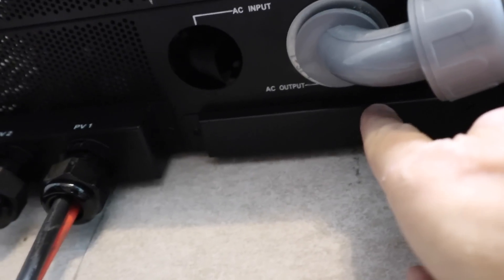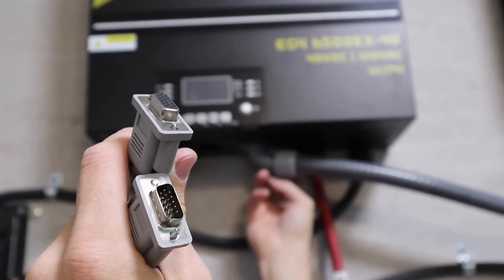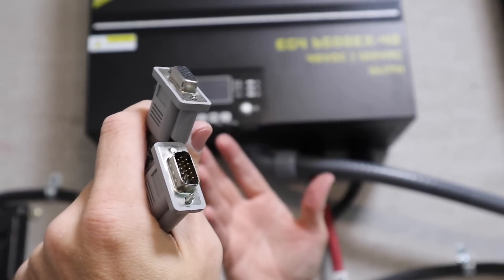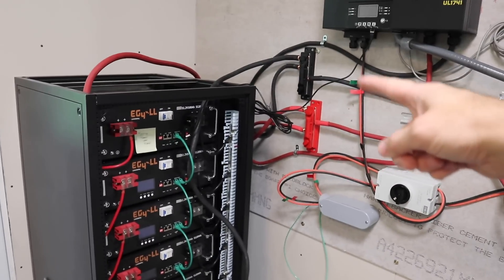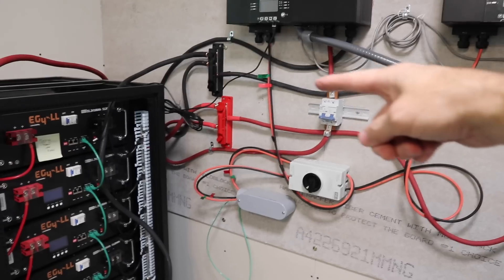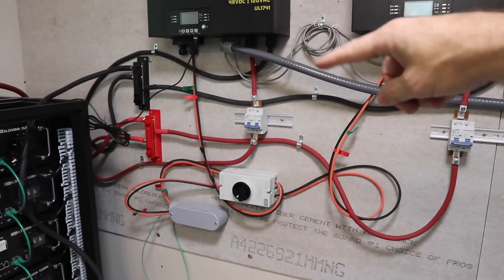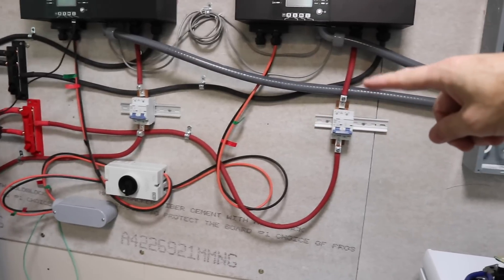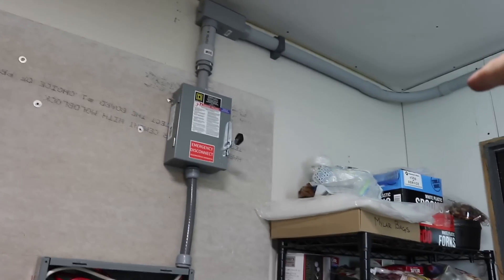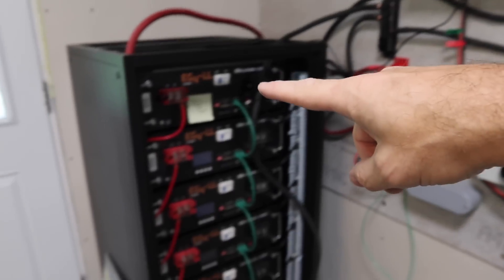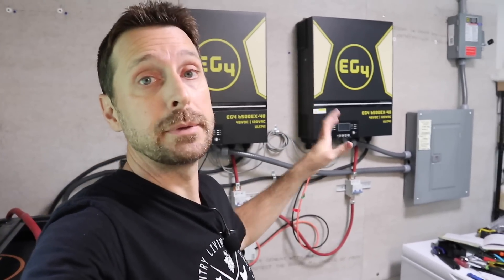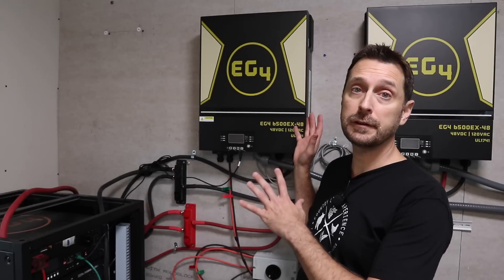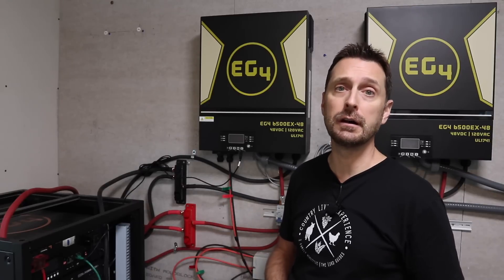Before I show you everything connected, we need to take this plate off right here, which exposes the paralleling ports. The paralleling cables have two different ends on them, and so do the connection points on the bottom of the inverters. So there's no way you can screw it up. Here is our battery bank connected to the other bus bars on the walls and our inverters batteries connected to those bus bars. We've got our PV connected to each inverter, our communication paralleling cables, and our AC out lines over to our load center, safety switch, and then back to our main panel. If you're interested in any of this equipment, click on the link in the description below to Signature Solar.